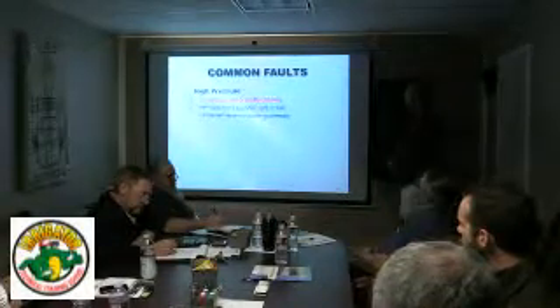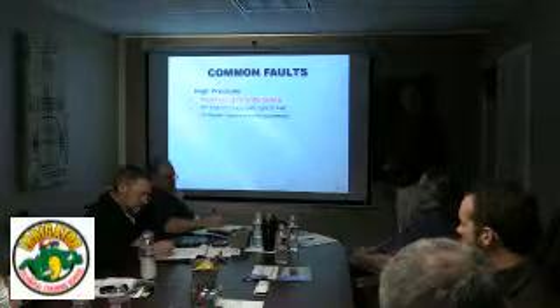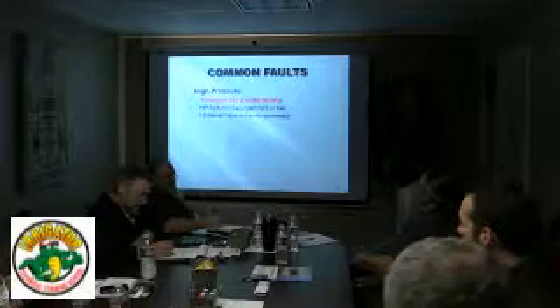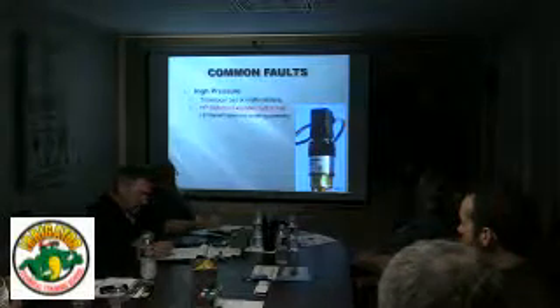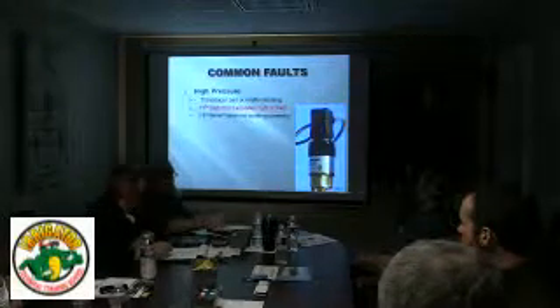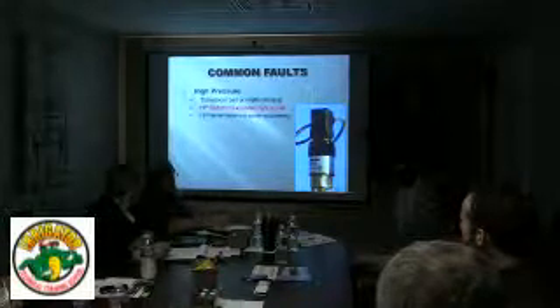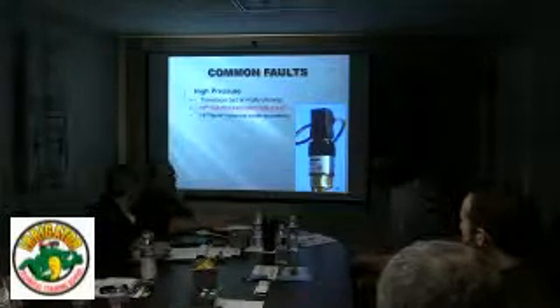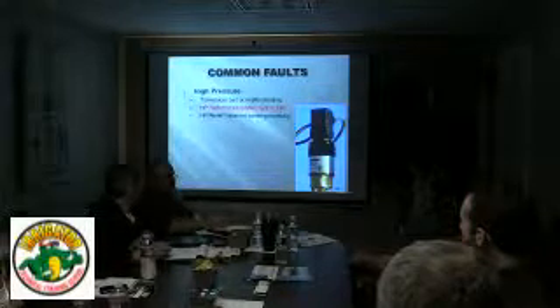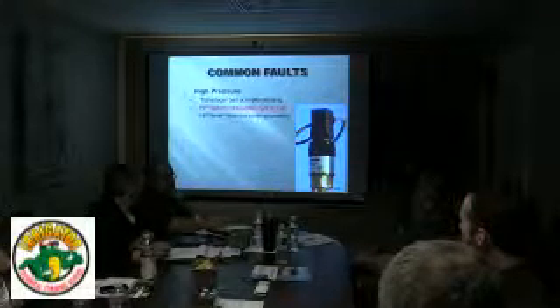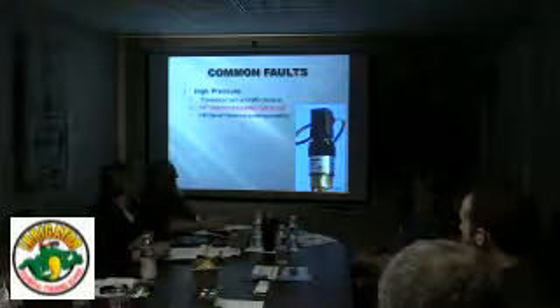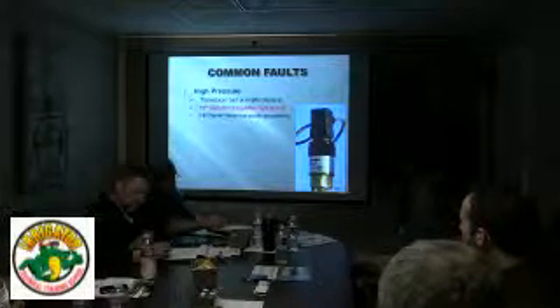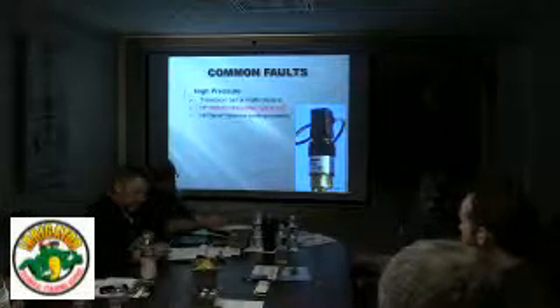High pressure faults, same thing: the transducer might be bad, or the high pressure switch is malfunctioning, or the high pressure relief valve's not working correctly. High pressure switches, this is the one that we use the most of. You see the knurls around the outside there; you just twist that to adjust it. Counterclockwise down, it increases the pressure; back up and it decreases the pressure.